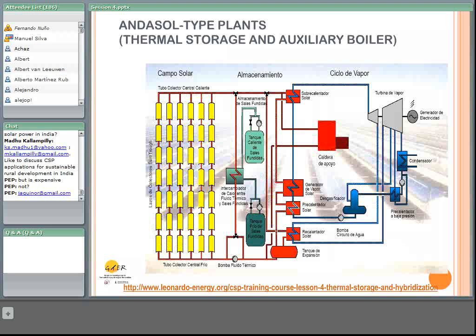Other reasons are that this auxiliary burner can be used to heat up the oil when necessary, and directly heat up the molten salts to avoid freezing. So it has different functions. In Spain, the natural gas heater is placed on the oil side.